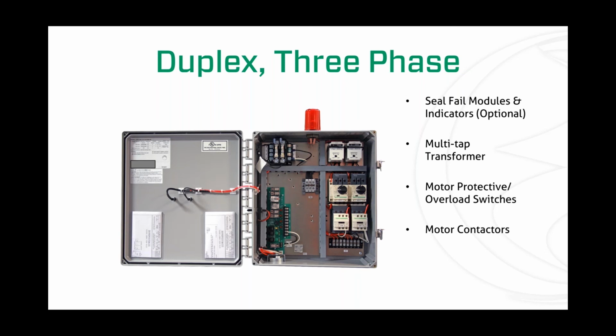This panel has the motor protective switches with the overloads. These look a little bit different than what we looked at previously. They actually have a little roll knob, and that is your circuit breaker and your overload all in one device. It has a little clear plastic window and a dial on it. You're going to have to turn those dials to your full load amp draw of your pump. From panel to panel, parts are going to look different, but their operation is going to be the same. Let's look here and go through these so you can actually see them.